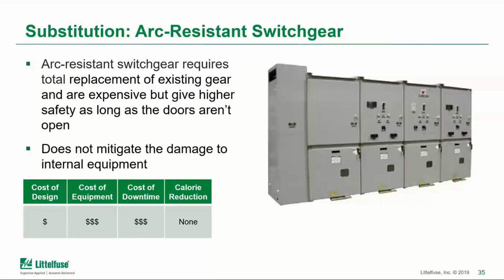Another form of risk mitigation that is popular in some applications is arc-resistant switchgear. This acts as a permanent layer of really effective PPE, as it contains and redirects that blast energy up or out and away from the workers. It can be vented outside, or just vented off to the side as well.